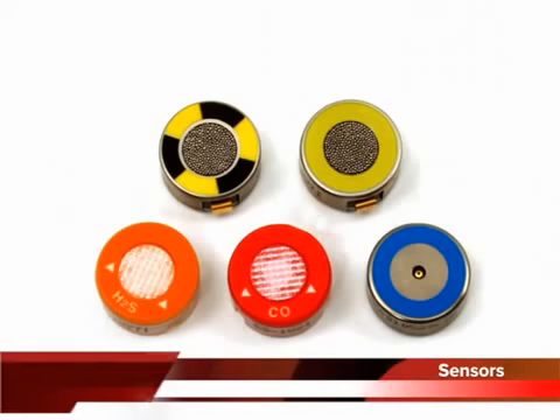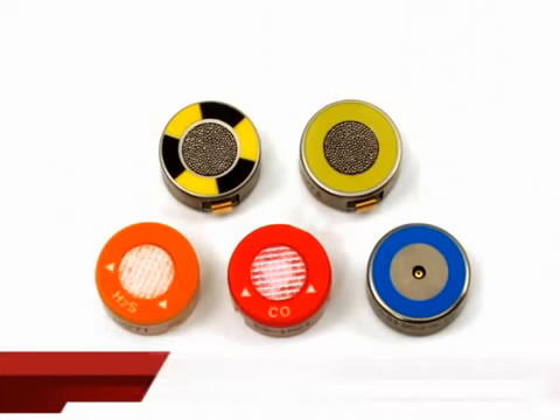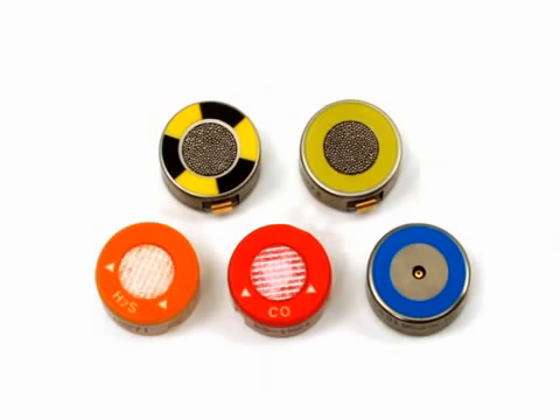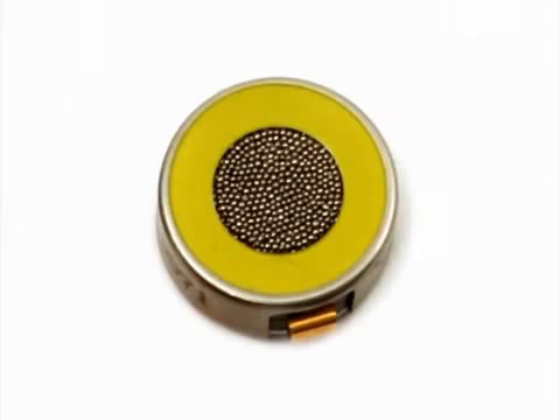The GX 2012 uses up to 5 sensors to monitor combustibles, oxygen, carbon monoxide, and hydrogen sulfide simultaneously. The combustible gas sensor detects combustible gas and vapors in the lower explosive limit range, or LEL, with a catalytic element.